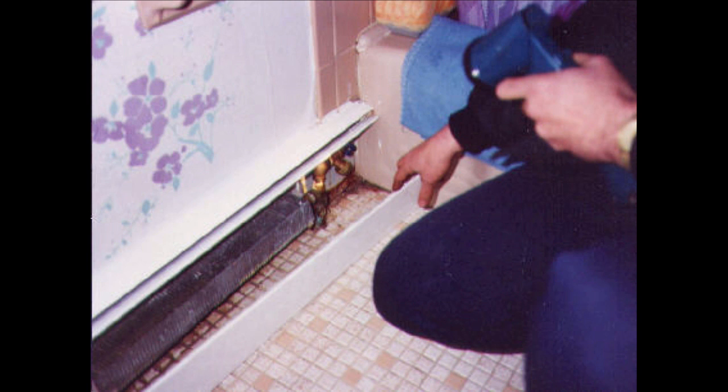And also while he's bleeding, he's not getting any air. So once again, if I don't get any air, it ain't an air problem. So I really should stop bleeding at that point. But this guy was persistent. So he got to a point where he said to the woman, I'm not coming back anymore. And he installed that boiler drain that you see here. And he left it with about four feet of a hose, a washing machine hose. And he said, listen, whenever you want heat, just put the hose in the bathtub and open this valve and run some water and the radiator will get hot.